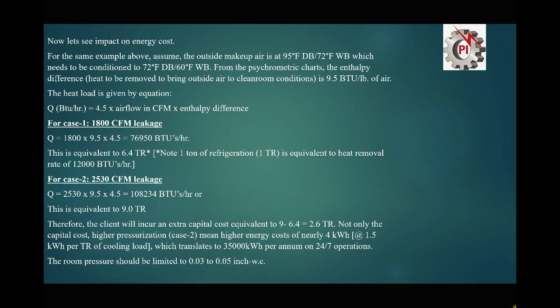The energy increase is 4 kilowatt hours, at 1.5 kilowatt per ton of cooling load, which translates to 35,000 kilowatt hours per annum on 24-hour operation. The room pressure should be limited to 0.03 to 0.05 inch of water gauge. We should not increase the room pressure more than this. If we increase the room pressure beyond it, we see how the energy cost increases, and how our electricity cost increases also.